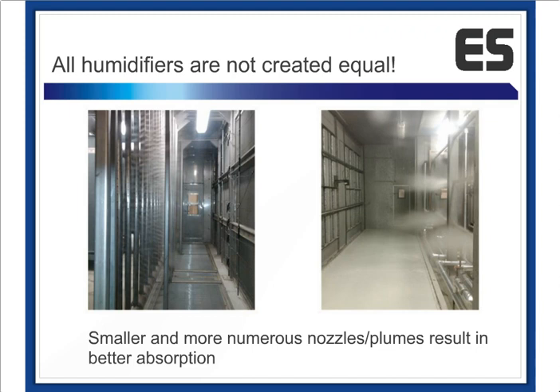Here are two slides showing the evolution of air handling unit humidification systems over time. The one on the right is a 1990 version air handling unit in a research facility. You can see how long the steam plumes are, how much space it physically takes for the steam to integrate into the airflow. The risk of pushing too much steam into a system like this is condensing on surfaces—warm, wet surfaces can lead to mold growth or other fungi.